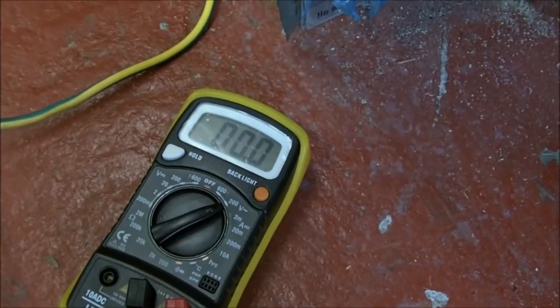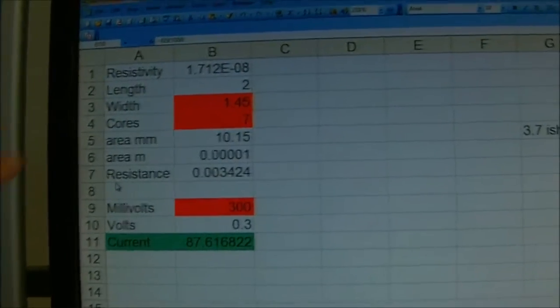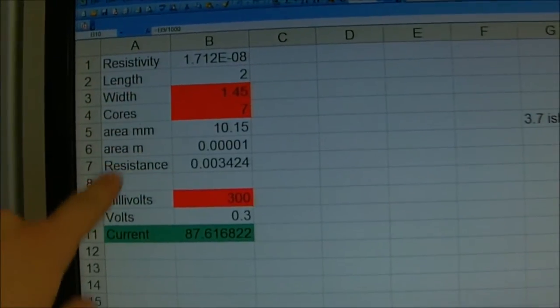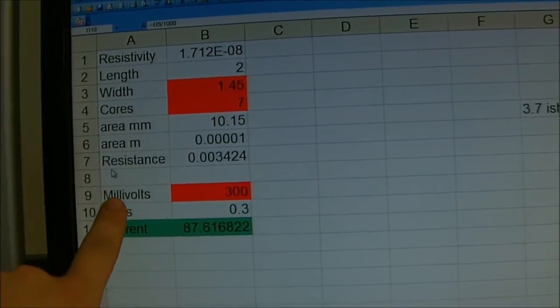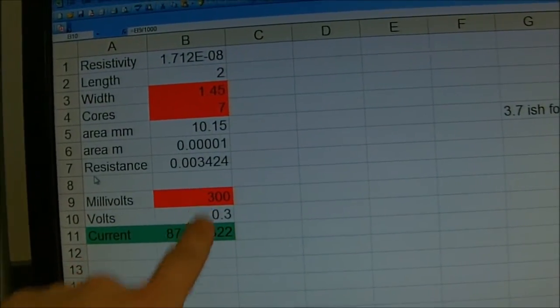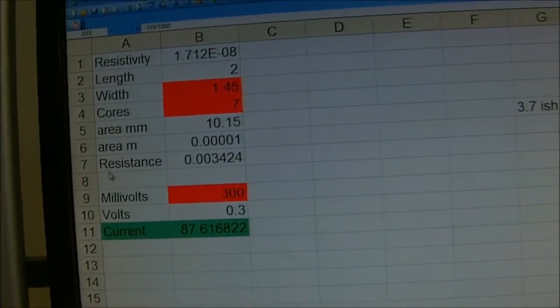So I'll just go and stick that into the Excel spreadsheet. Into the spreadsheet, all the same values as before for the width, cores, and the resistivity of copper. We got 0.3 volts which is 300 millivolts, and that reckons it is 87.61 amps.